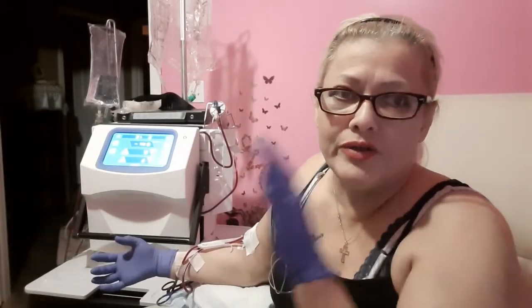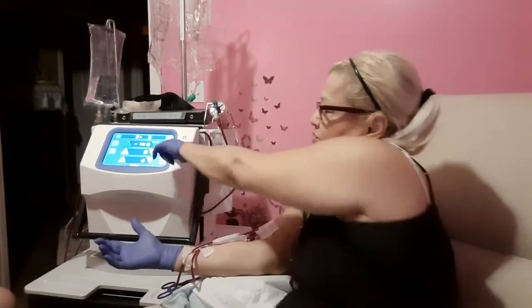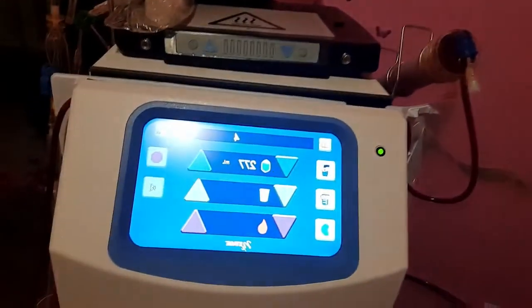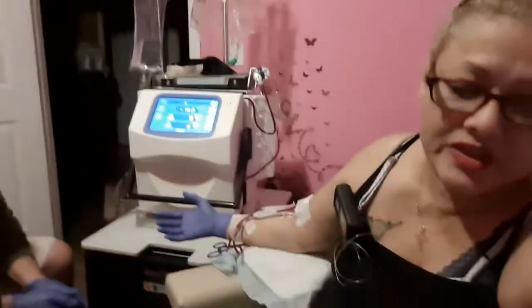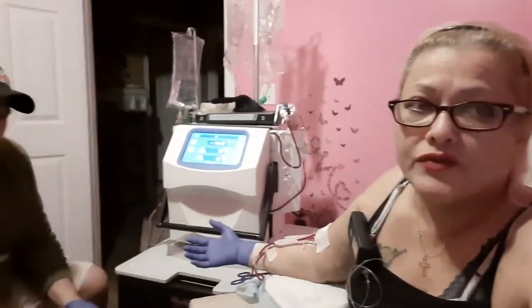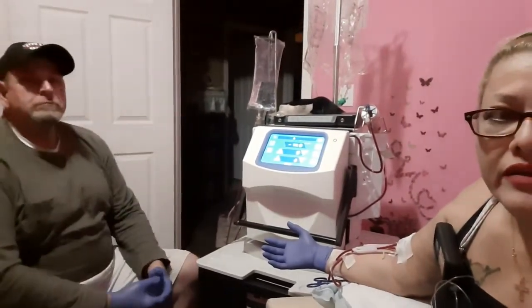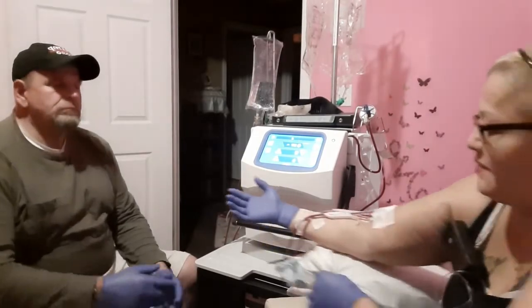Okay, everyone, so now I've ended treatment. Everything is at zero. Hubs has to press the stop button, so that's my rinse bag volume. Let me show you real close. It says 277. Okay, but before we can rinse back, we have to take care of the arterial first. So I'm going to kind of go like this so that you can see Hubs and I at the same time.